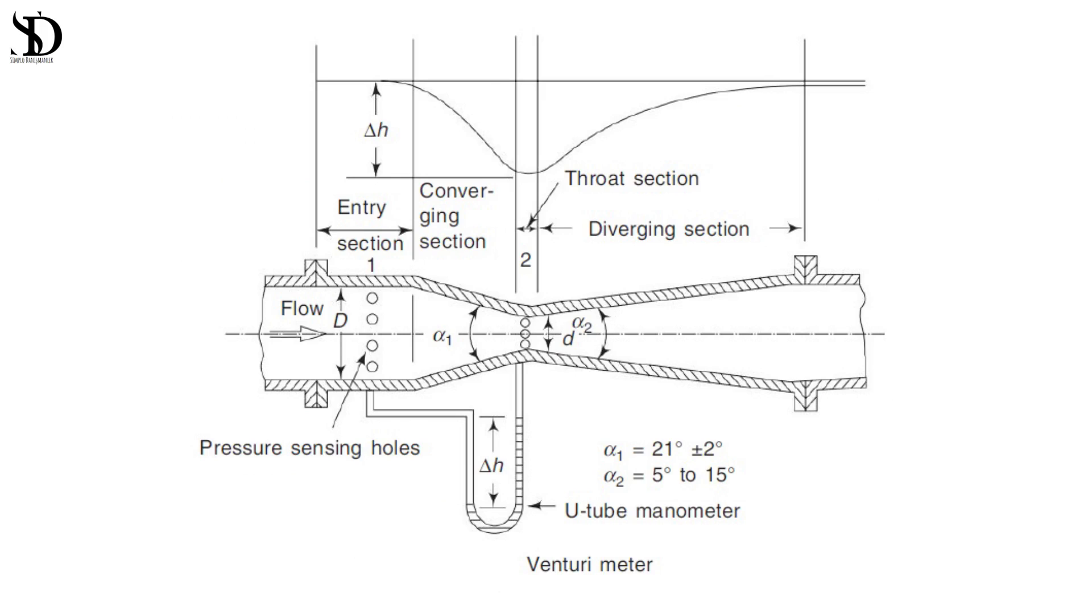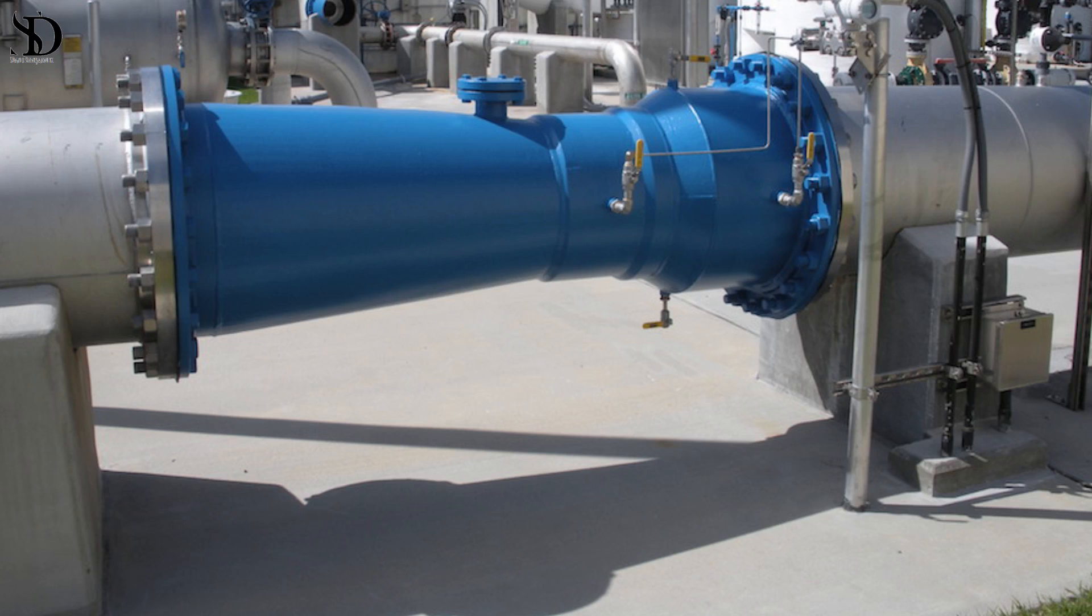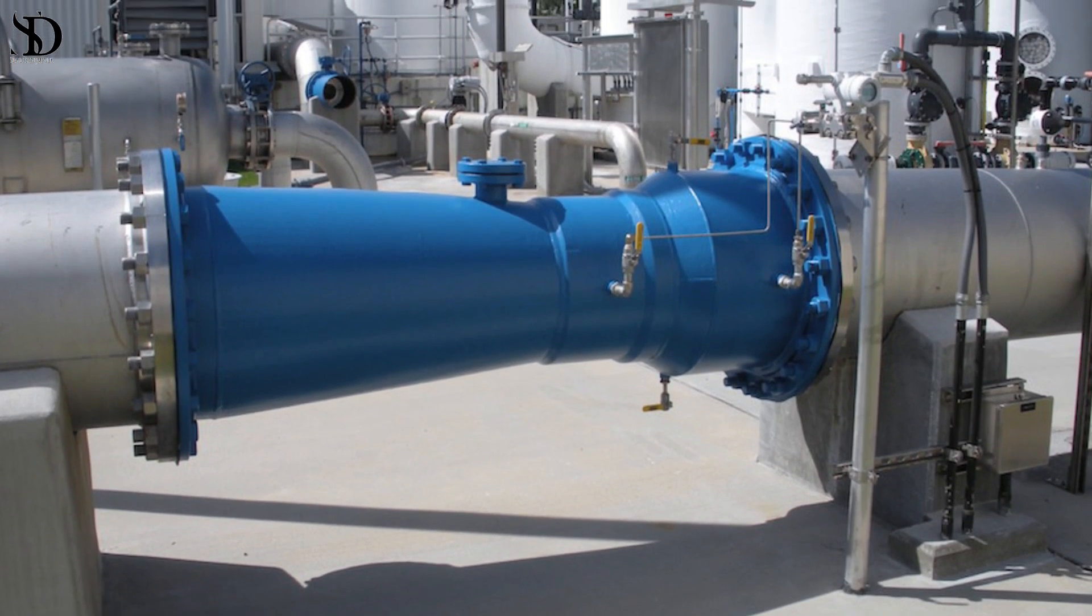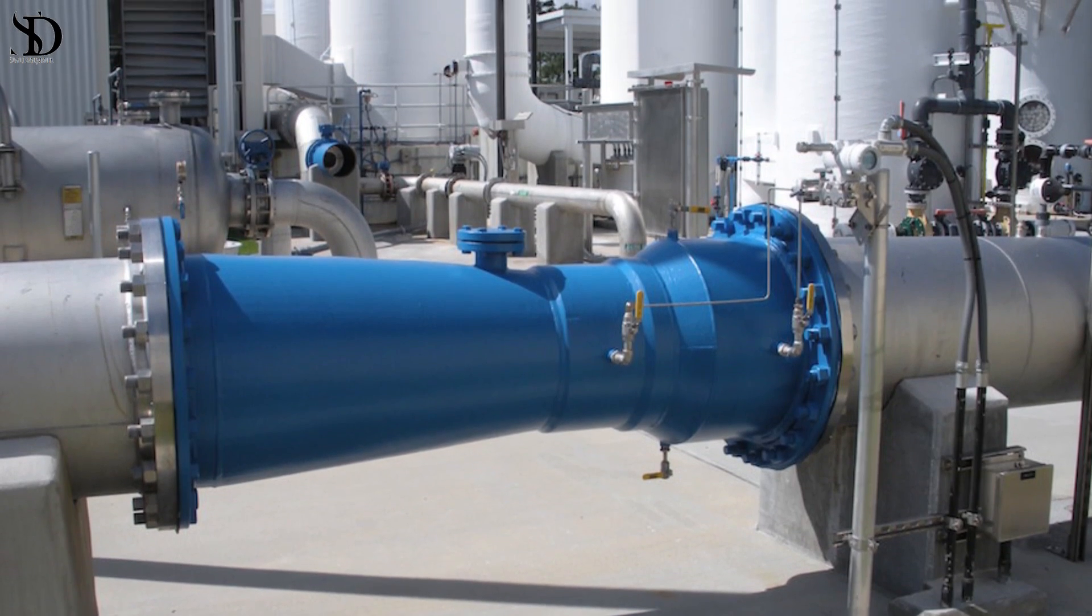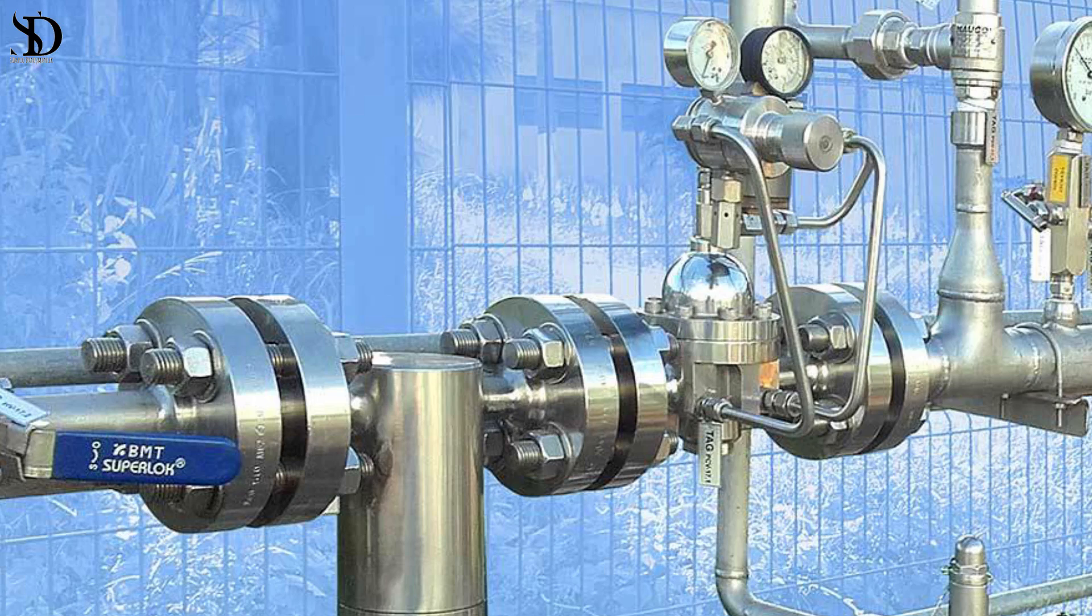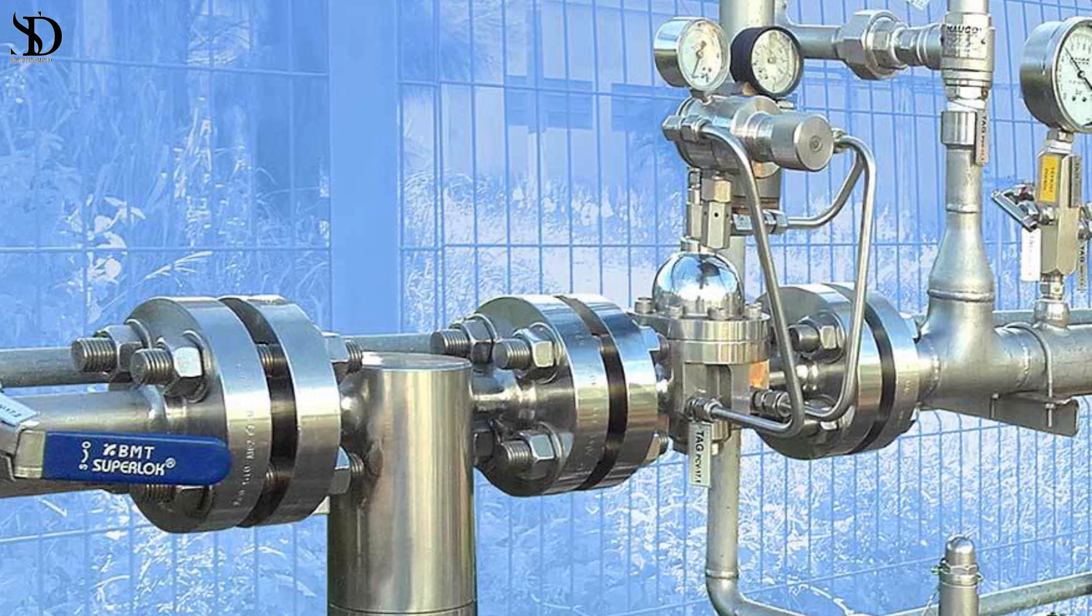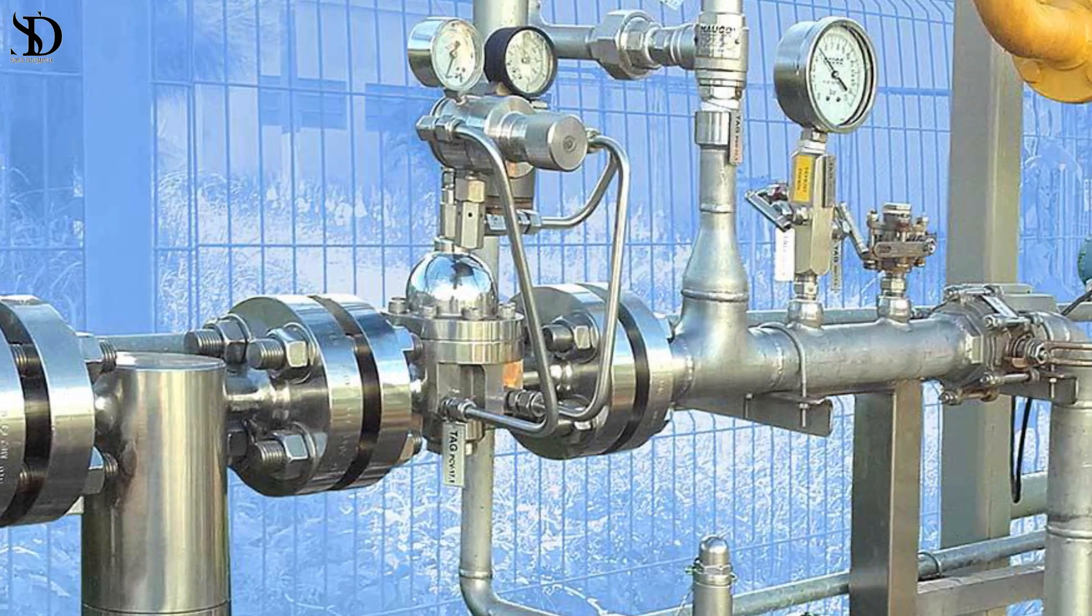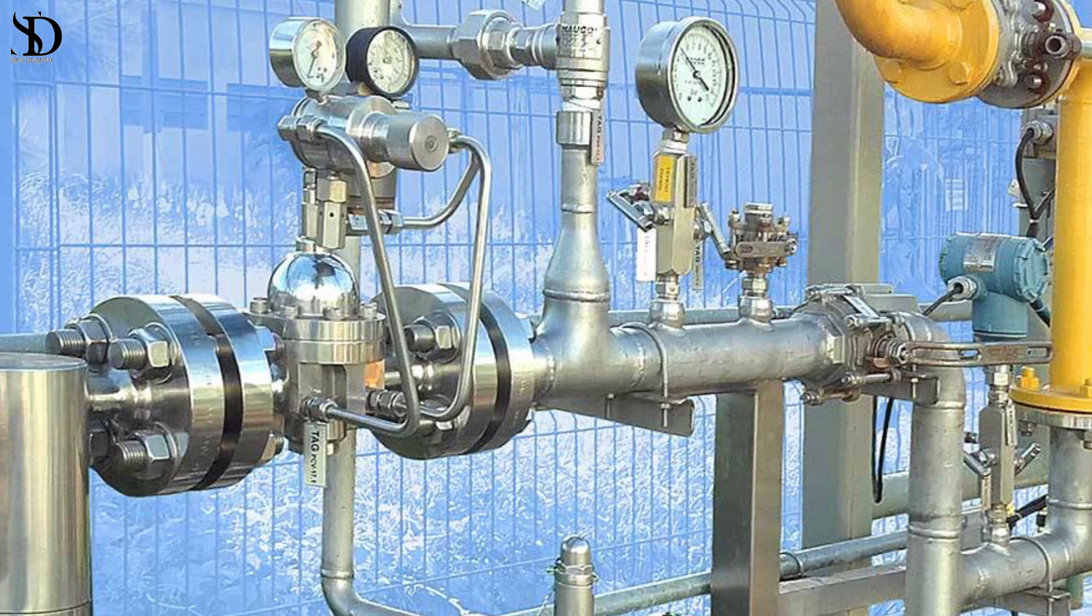Flow efficiency: venturi tubes offer enhanced accuracy due to their streamlined design, allowing for minimal pressure loss compared to orifice plates. Size and installation: venturi tubes require ample space for installation due to their structural design, making them less suitable for constrained spaces. These tubes are favored for applications requiring higher accuracy, such as in the measurement of clean liquids or gases, however their installation cost and space requirements might be higher compared to orifice plates.